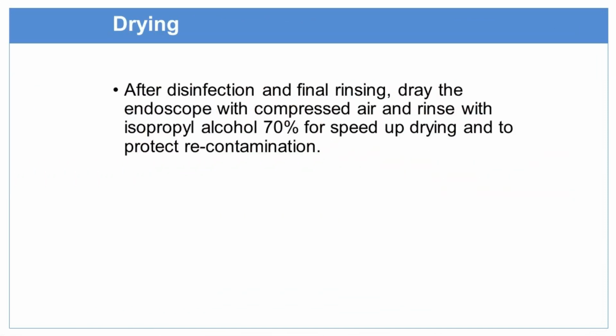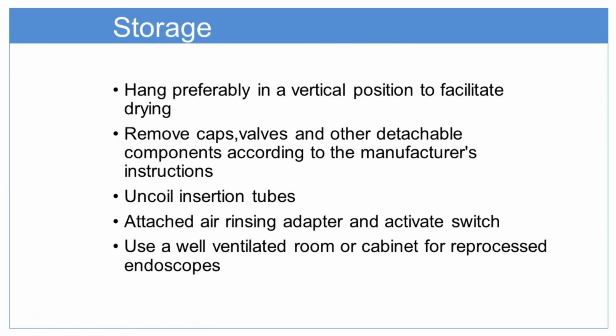Then dry all the endoscopes after passing all this process. It must be dry. After disinfection and final rinsing, dry the endoscope with compressed air and rinse with isopropanol alcohol 70% to speed up drying and to protect against recontamination. After all this, how will we store the endoscopes after cleaning?